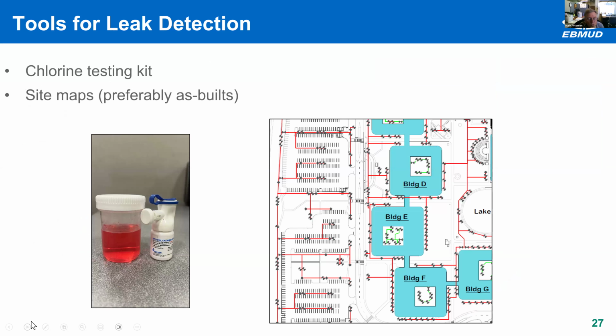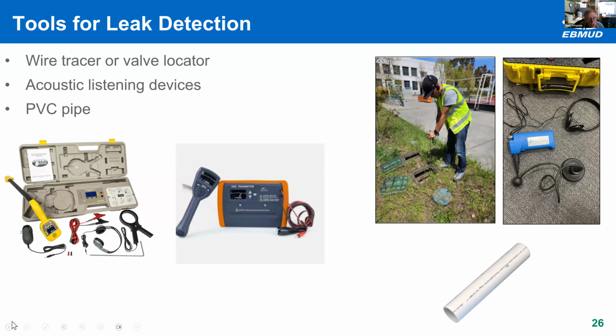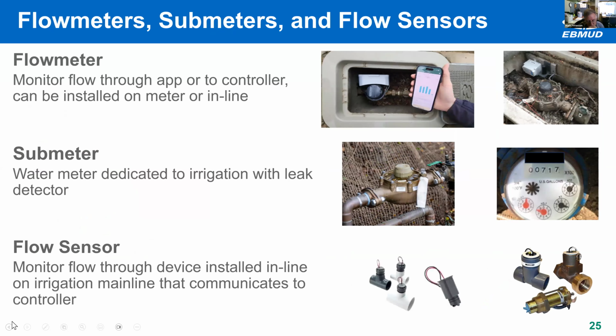And going back 2 slides, the flow sensor, flow meter, something that I've had to wrestle with is that these things have certain ranges that work. If the flow sensors are 1.5 inches and larger, they're not going to record very well anything under 1 or 2 gallons a minute. And it's a dilemma sometimes. You have a flow sensor, but you can't measure the small stuff. Yeah, absolutely.